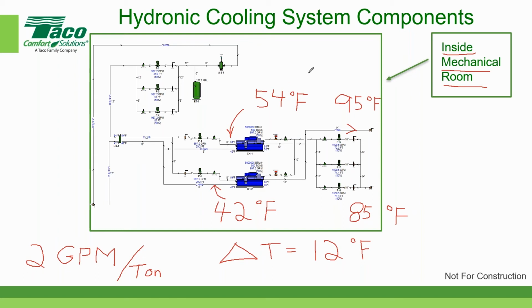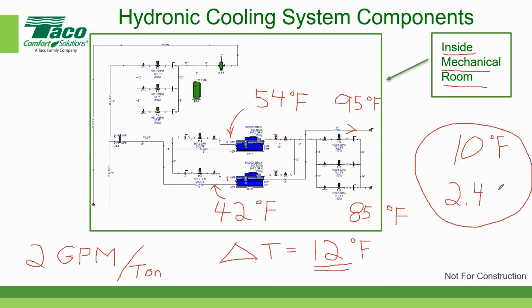That's how you can quickly estimate how much flow you're going to need for a chilled water system that uses a 12 degree delta T. And by the way, just for the fun of it, if you're using a 10 degree delta T, the lower the delta T, the higher the GPM per ton is. So that would be 2.4 GPM per ton. At 10 degrees delta T Fahrenheit, that would be 2.4 GPM per ton. I'm not going to put all the labels in there. And by the way, a couple of comments, and I like some of these right here. I like them all the time. One gentleman said, and it's 12.2 degrees Celsius.